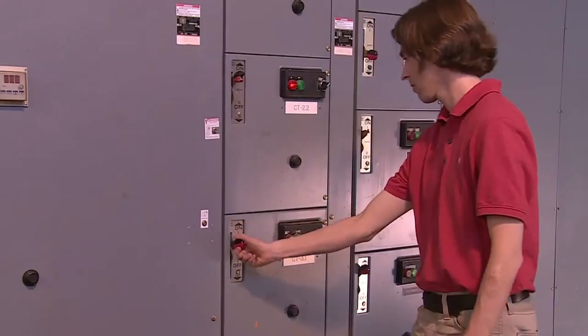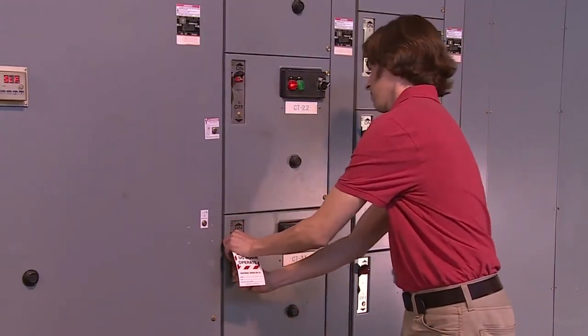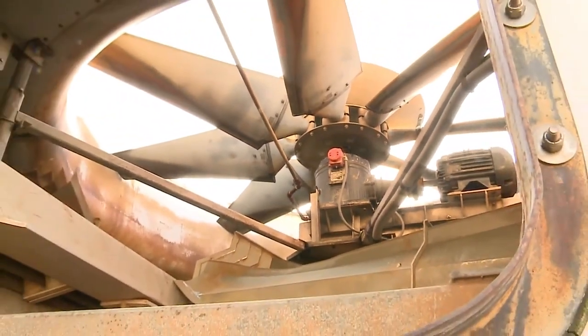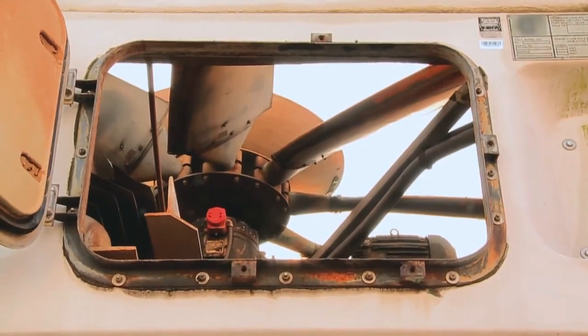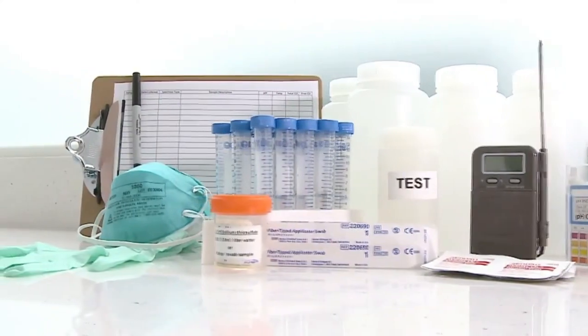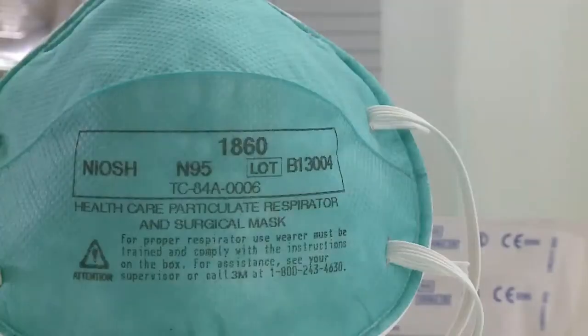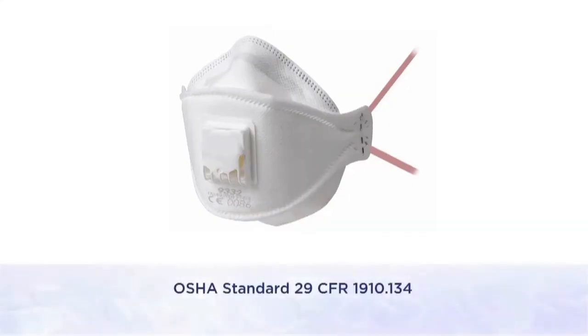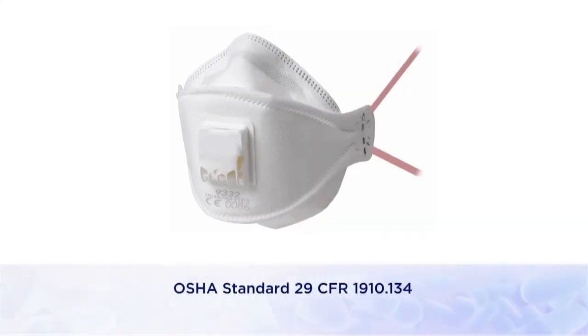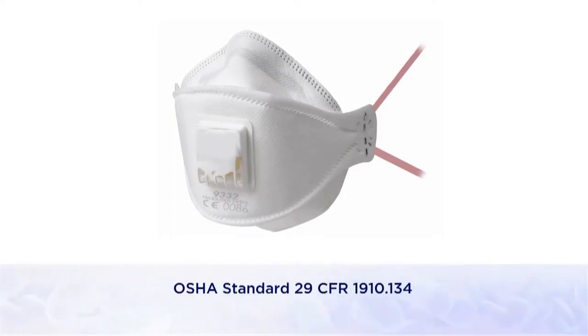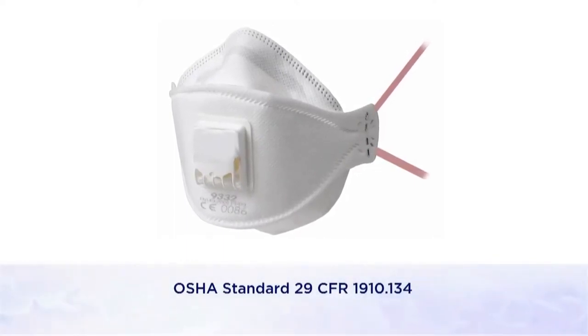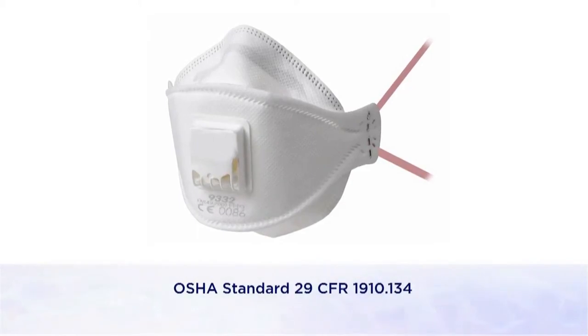Please be mindful of safety issues when sampling cooling towers, since they can be located in maintenance areas and on rooftops. When practical, cooling tower fans should be turned off to stop the spread of aerosols that may be contaminated with Legionella. When fans cannot be turned off, wearing a half-face air purifying respirator equipped with an N95 filter may be appropriate. Respirators must be used in accordance with a comprehensive respiratory protection program, which includes fit testing, training, and medical clearance ahead of their use.